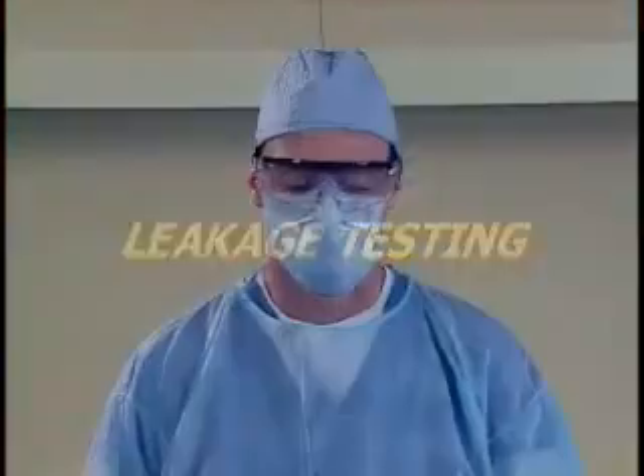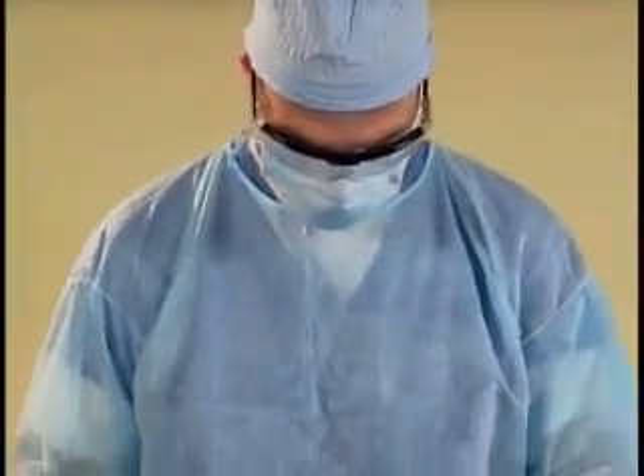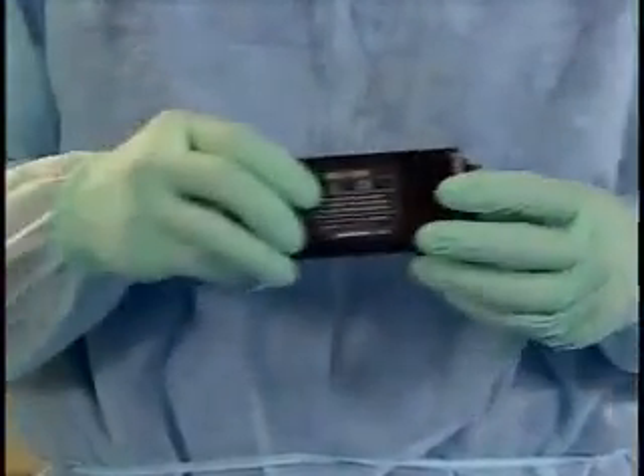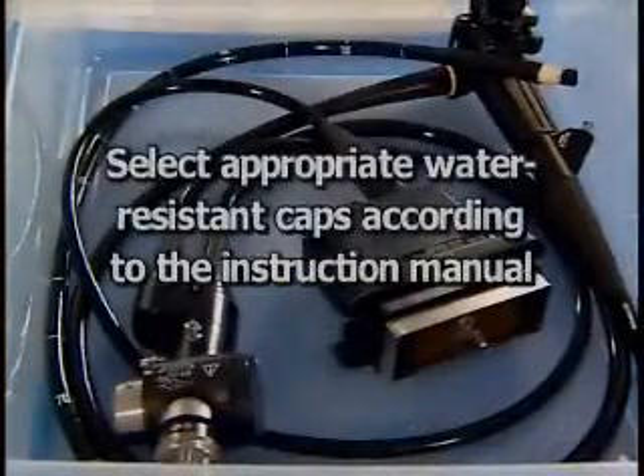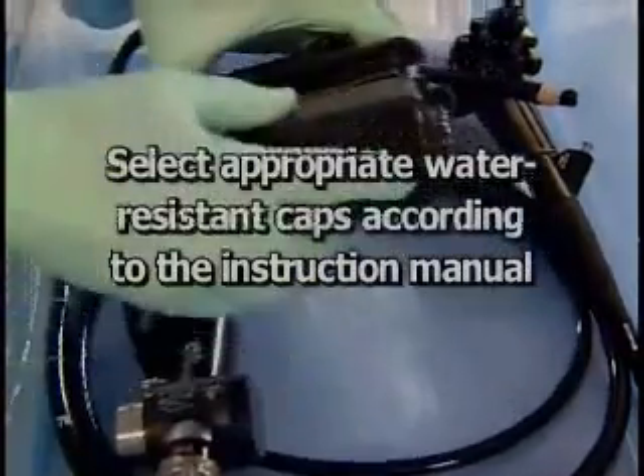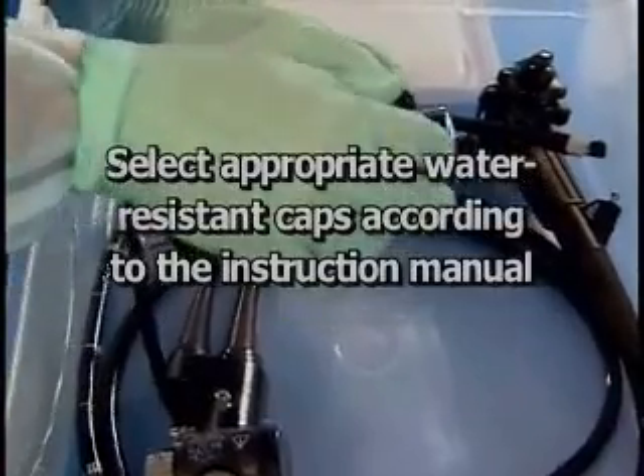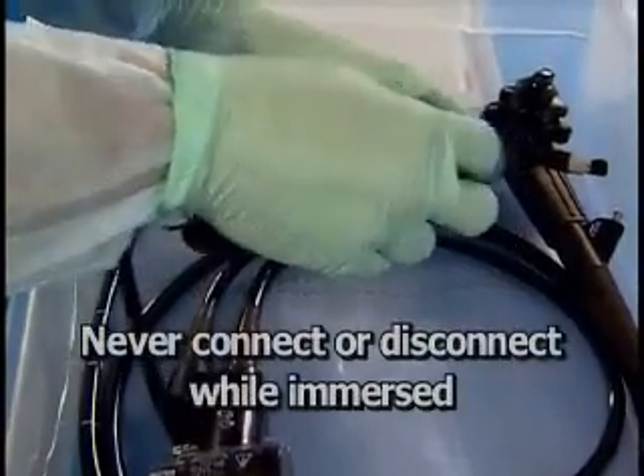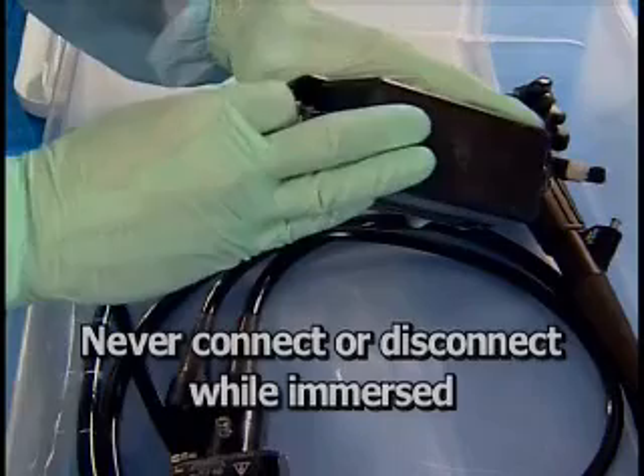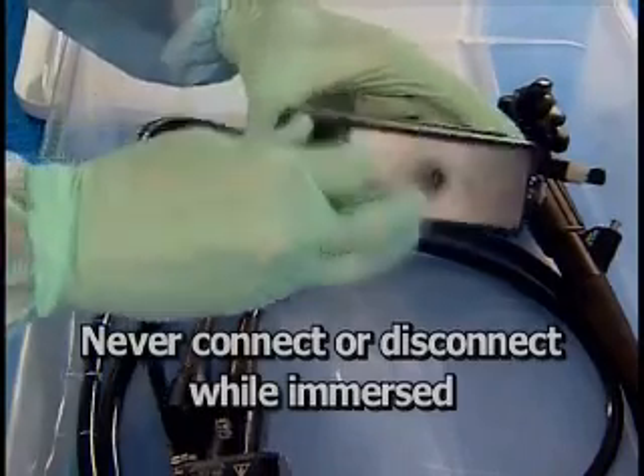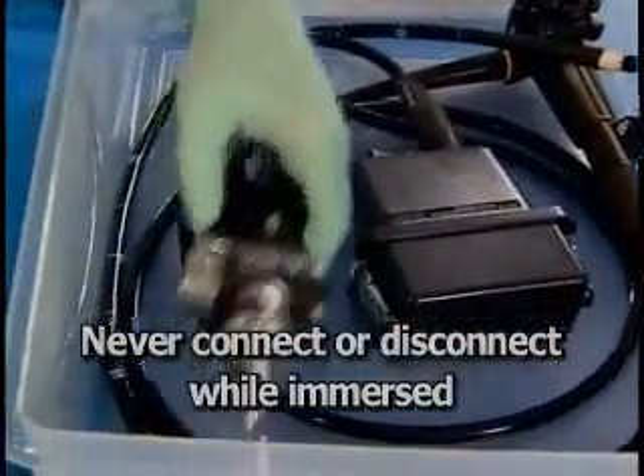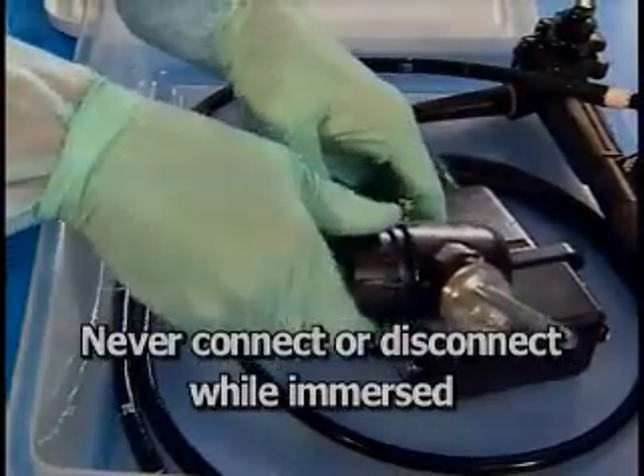Steps should be performed prior to immersing your videoscope in any fluid. Visually inspect the water-resistant caps for damage. If any of these are damaged or wet, use another cap. Attach the appropriate water-resistant caps to the endoscope. Remember, never connect or disconnect the water-resistant cap while the cap or the endoscope is immersed. Doing so will damage the endoscope.